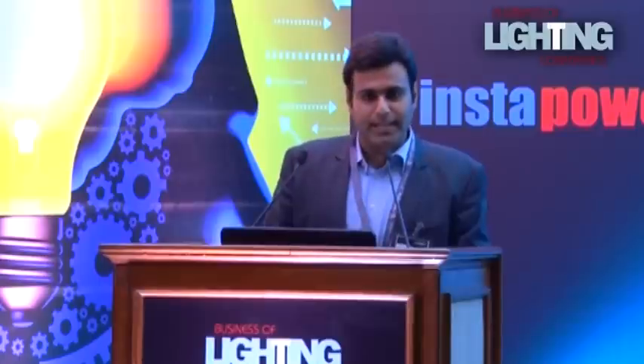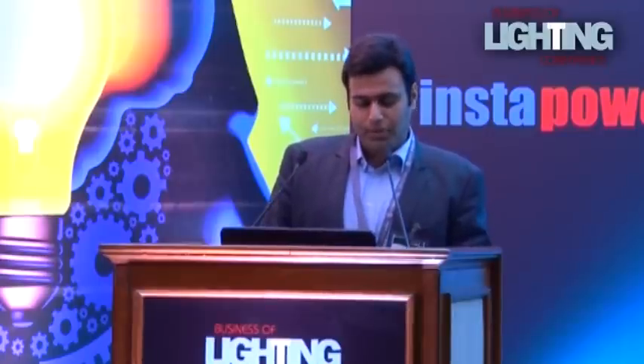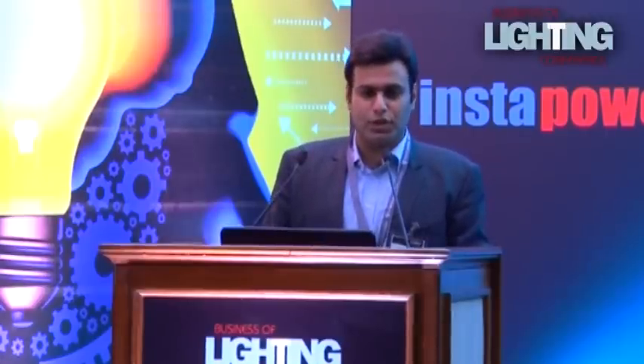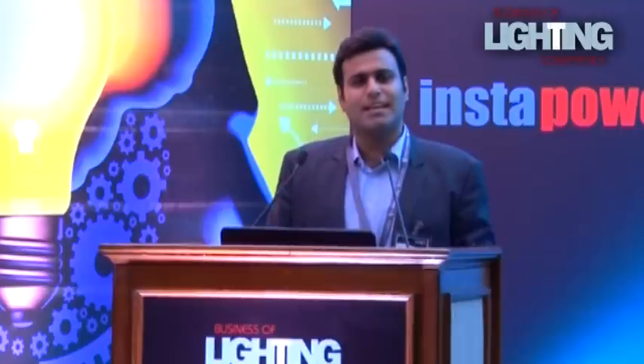On integrating my daylight sensors to the building, I've brought down my EPI to 115, from 215. My HVAC load is almost half, to 285 TR, and my CO2 emissions have reduced almost by 40%, to just 937 tons per year. So we've come down from 4-digit CO2 emissions to merely 3-digit CO2 emissions.